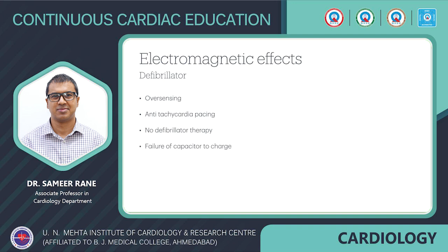Then, a power on reset is a specific type of reprogramming that reverts the device to factory default settings when battery voltage falls below a critical level or damage to the circuits is detected. This is a fail-safe feature and was seen in older devices manufactured before 2002. The settings to which the device reverts vary by manufacturer, and many devices reset to inhibition pacing with anti-tachytherapy on, where the device will initiate therapies for life-threatening arrhythmias.